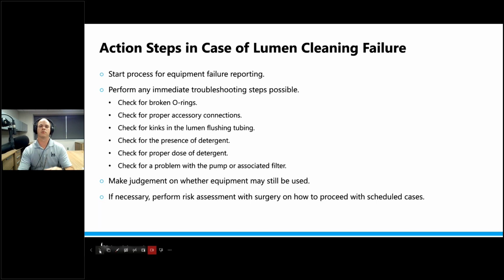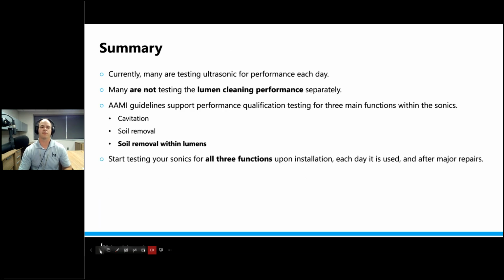working. So in summary, remember, currently many are testing their sonic for performance each day, but many are not testing the lumen cleaning performance separately, which they should. AAMI guidelines support testing for three main functions: cavitation, soil removal, and soil removal within lumens. And start testing your sonics for all three functions upon installation, each day it's used, and after major repairs.